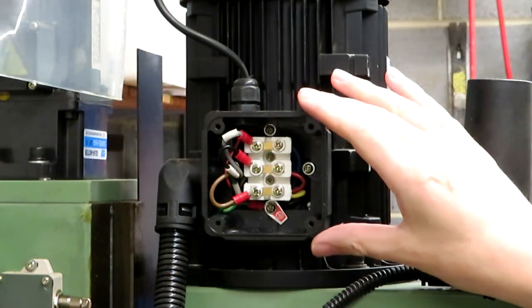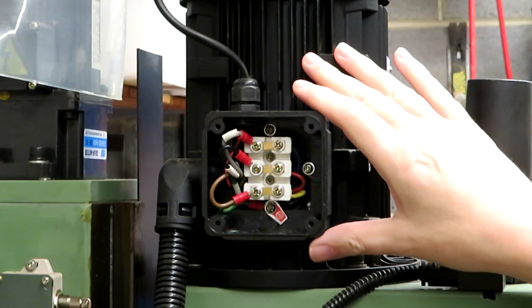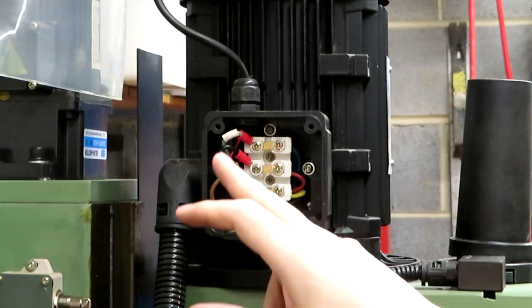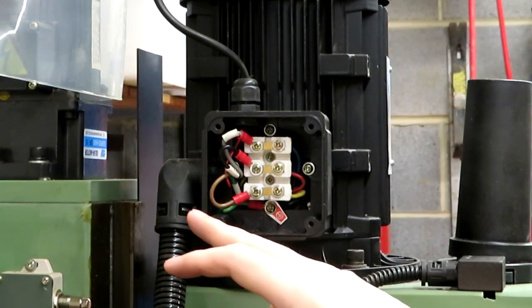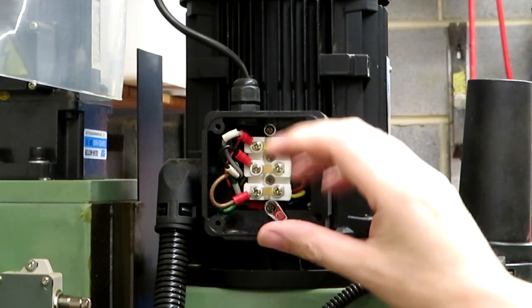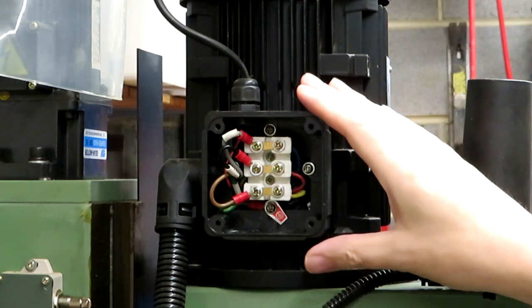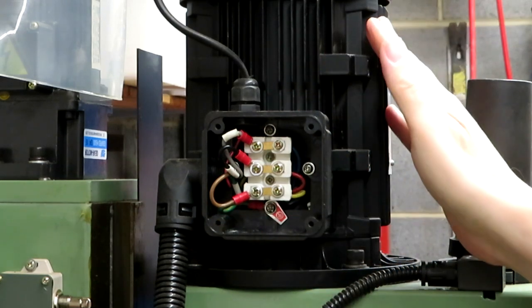So I've just removed the lid from the terminal box of our three-phase electric motor, and you can see that we've got three wires here. We've got a grey, a black and a brown. Each one of those is one of the three phases which has been supplied from the VFD to this motor.